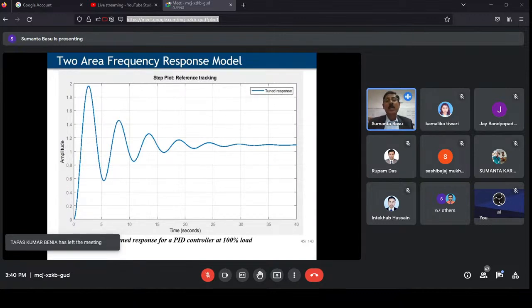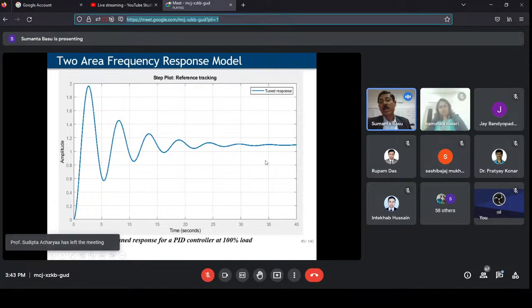So this is an ideally tuned response of your steam turbine generator. You see that within almost 35 seconds, the system frequency gets stabilized. If we remember the first slides where I had shown that secondary frequency response has to be within 5 to 30 seconds to bring back the frequency, here you see that practically it is taking around 35 seconds to stabilize the frequency.